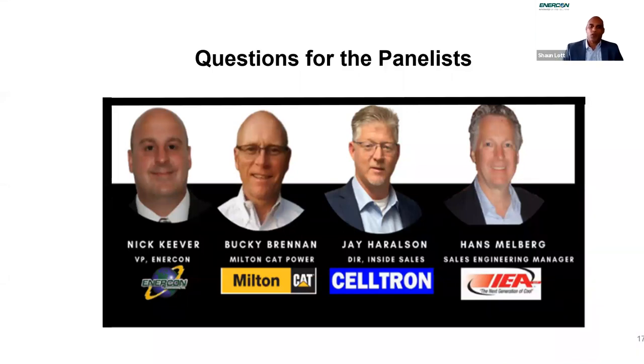Our next question deals with sound. What solutions do you typically use to enhance sound attenuation in tactical generator cells? There are a couple of different approaches depending on the amount of sound your prime mover outputs versus your requirement. Most typically, it's a mineral wool substance inserted into the walls of the enclosure with perforated metal over top, allowing sound to dissipate through the mineral wool. Also, as Hans touched on, when you're moving a lot of air and you open up areas, that produces opportunities for sound to leak. So you want to minimize open areas in the package, and ensure good sealing methods around doors and any access points inside the package.